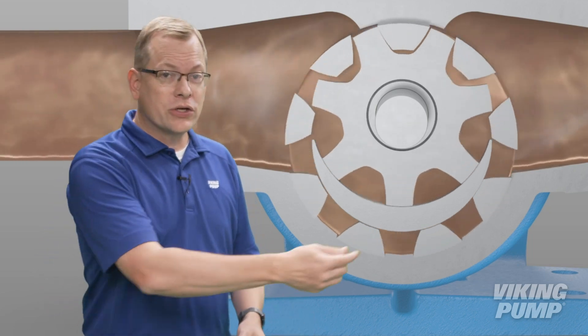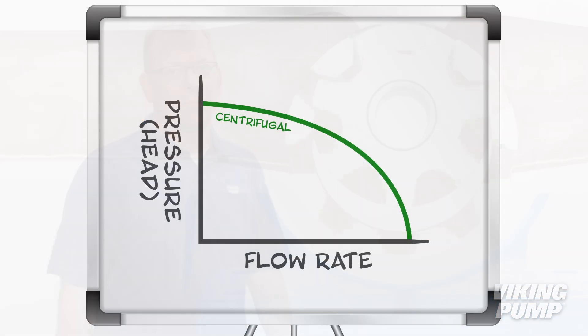These are flow-creating machines. With each rotation of the pumping elements, a set volume of liquid is transferred from the inlet pipe to the outlet pipe. Overlaying a Viking pump curve on a centrifugal pump curve, and you don't get a curve at all. Instead, we basically get a vertical line at one set flow. This overlay helps to demonstrate just how different these technologies are in how they move liquids.